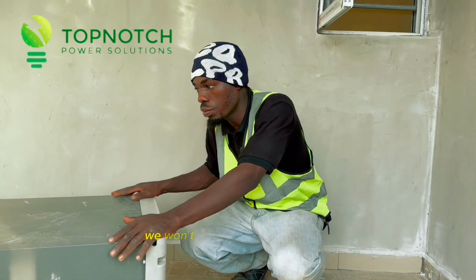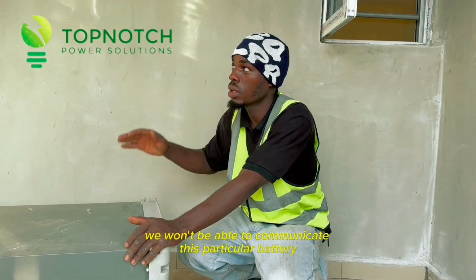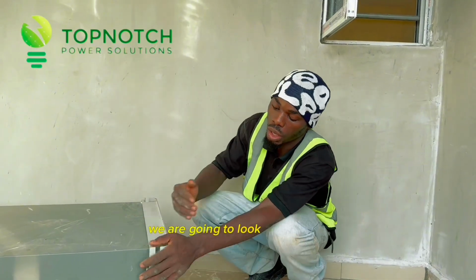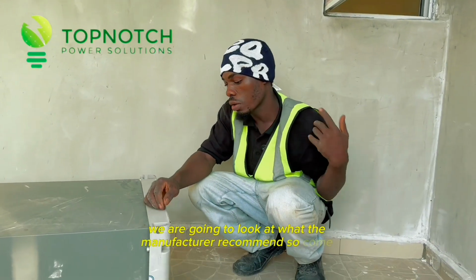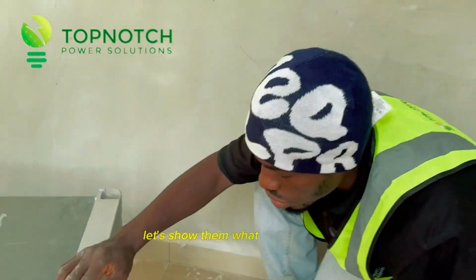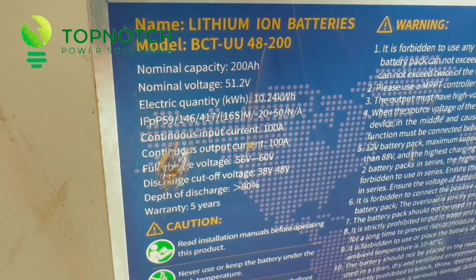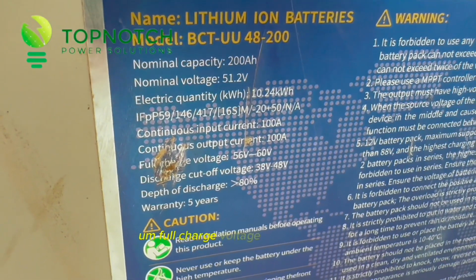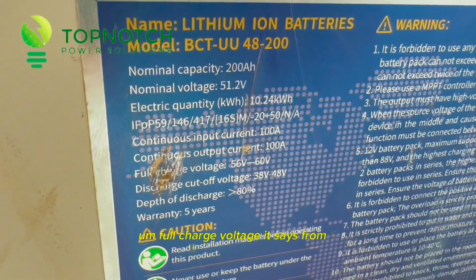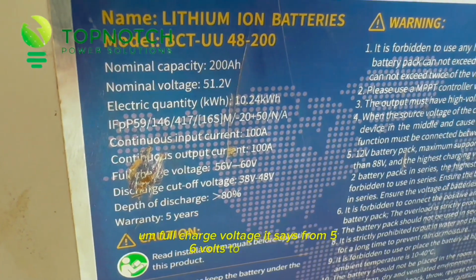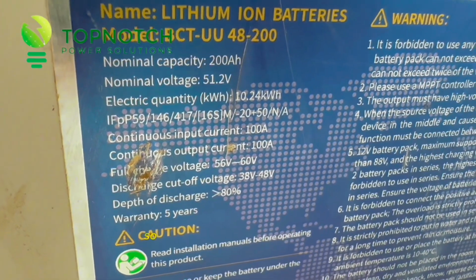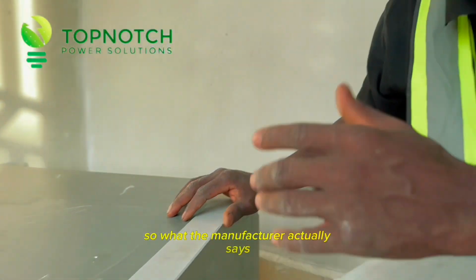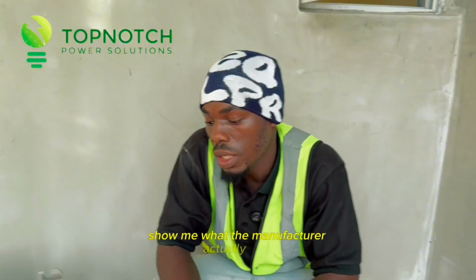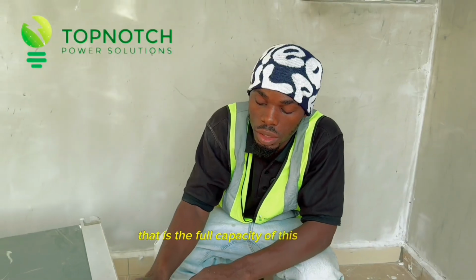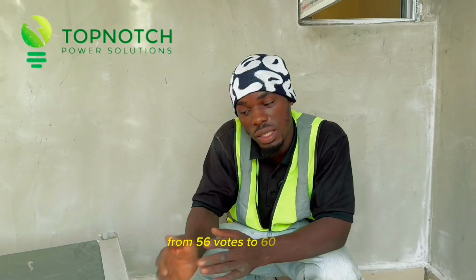So based on that, since we won't be able to communicate this battery with the inverter, we are going to look at what the manufacturer recommends. Come close, let's show them what the label says here. Full charge voltage, it says from 56 volts to 60 volts. So the manufacturer says the full capacity of this lithium-ion battery is from 56 volts to 60 volts.